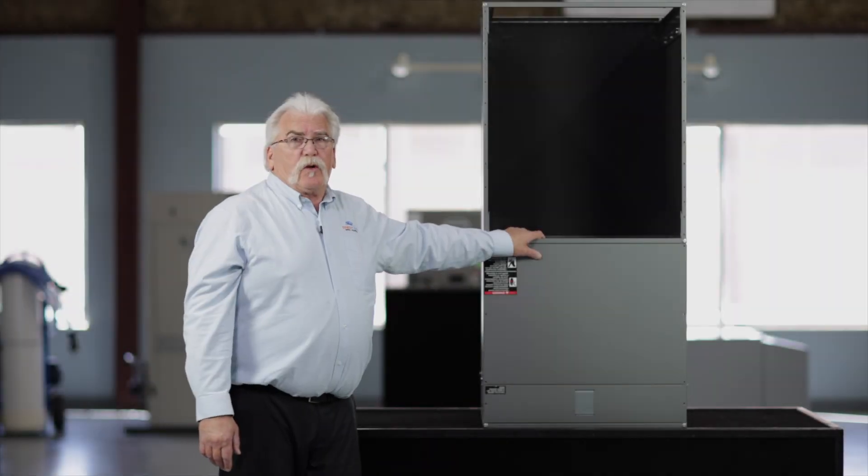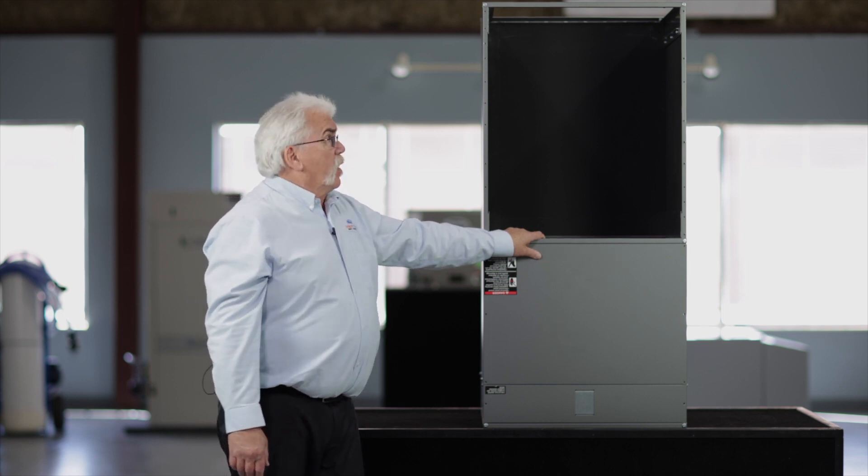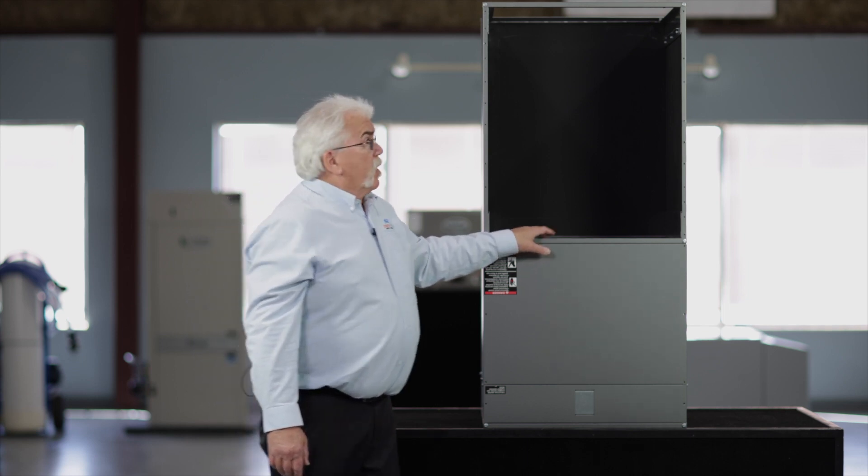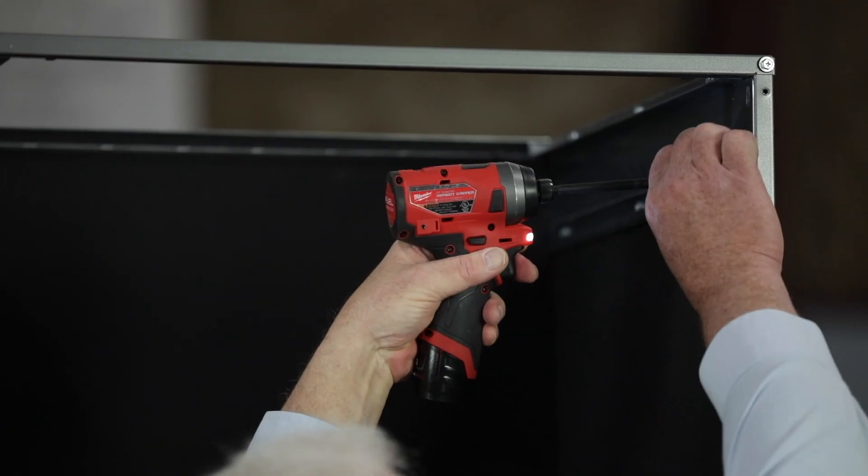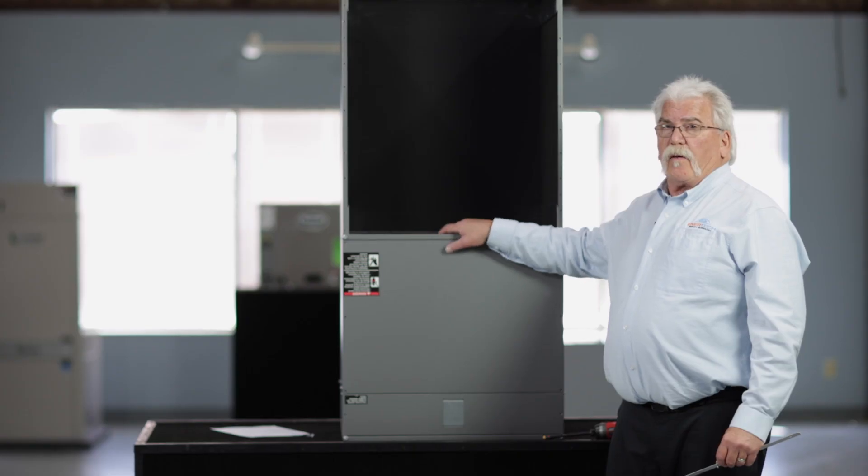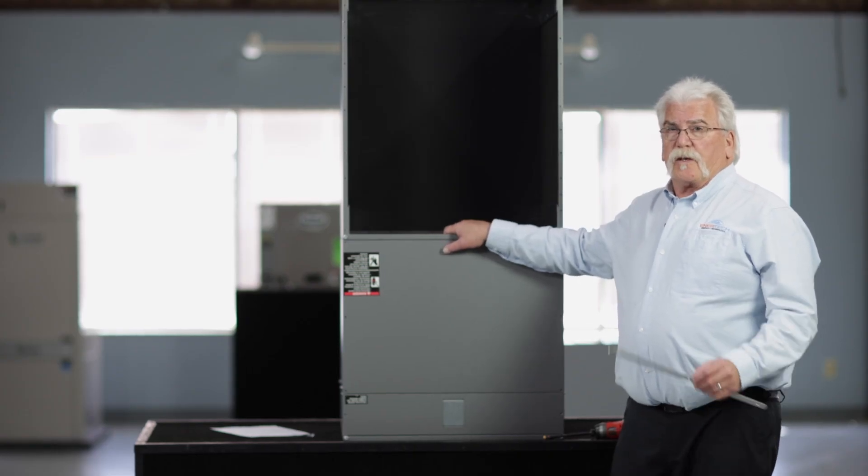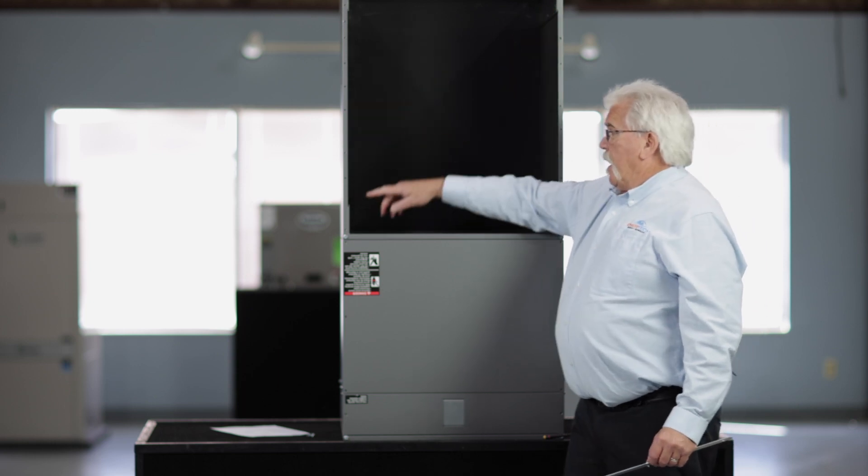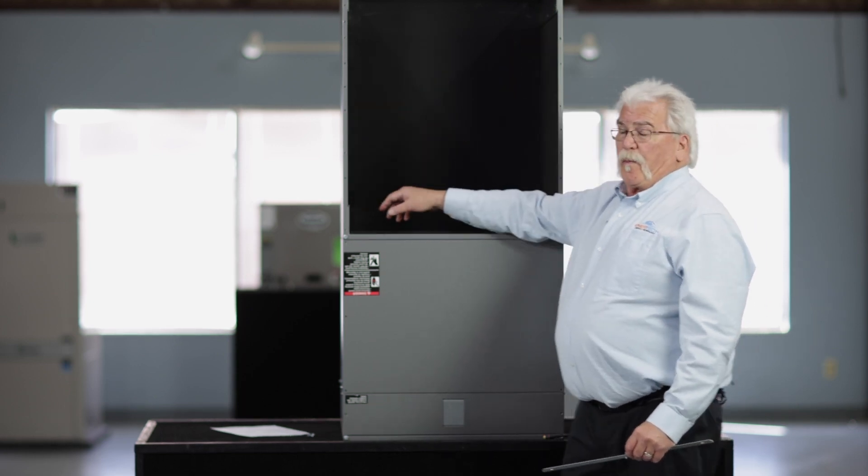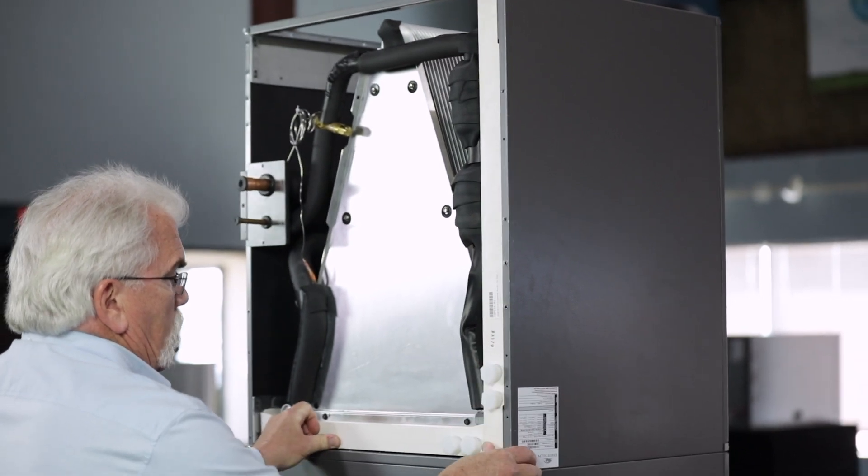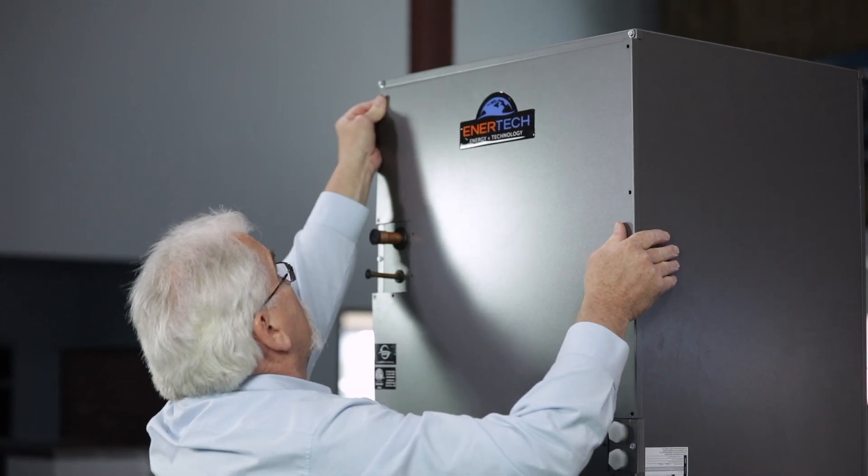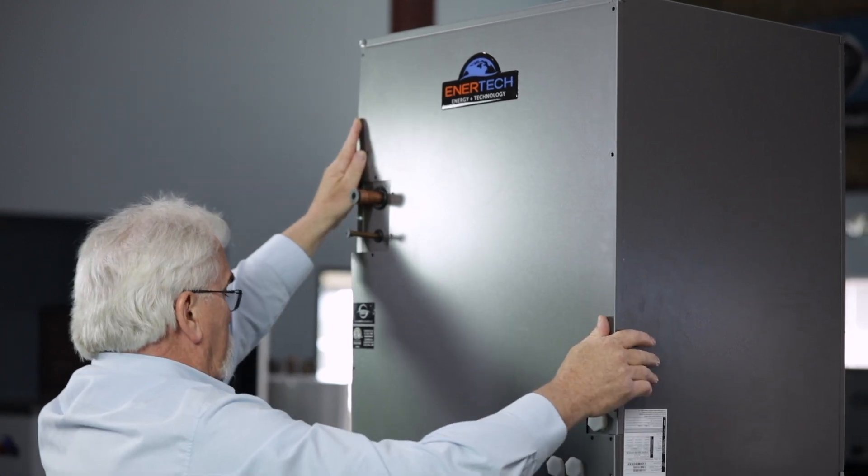So now that we've flipped the unit into a downflow position and removed the A-coil, there's a small rail up top that needs to be removed and will be reinstalled with the A-coil in its new configuration. Now that we've got the unit in the downflow position, we've removed the rail from the top and need to reinstall it on the left bottom. The cover fits right back over the top once the A-coil is installed.